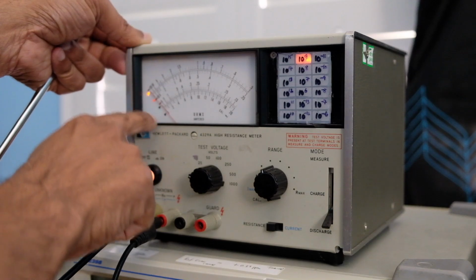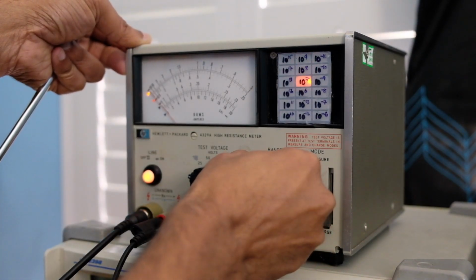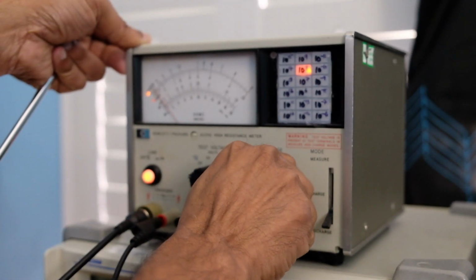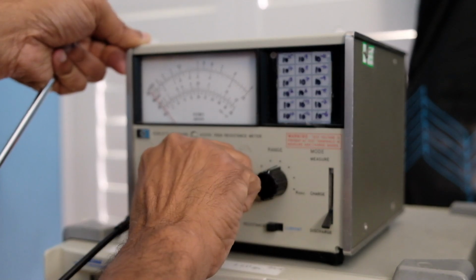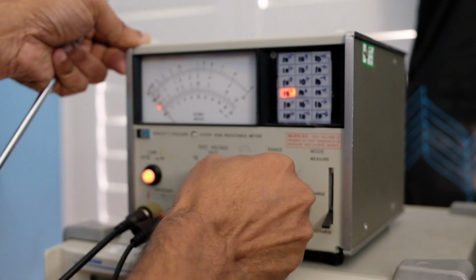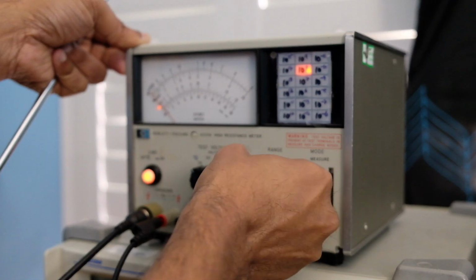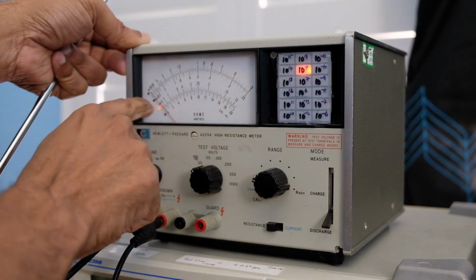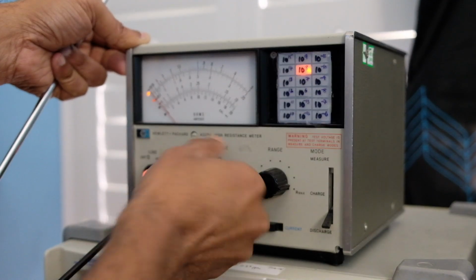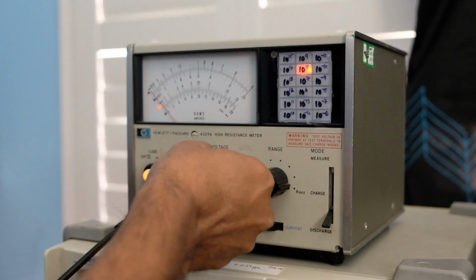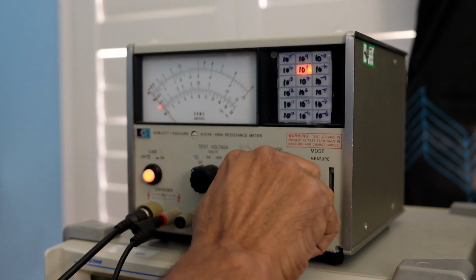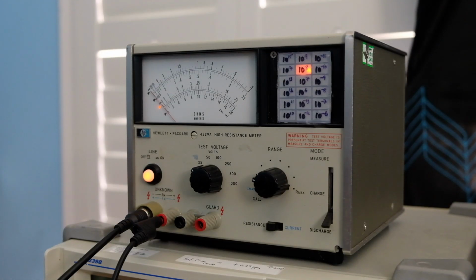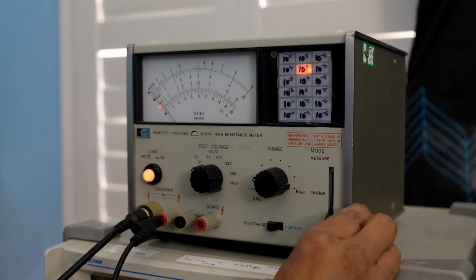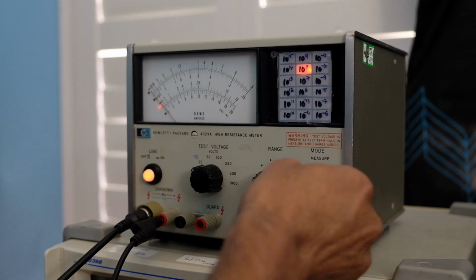So you can see on the left side over here the scales that are being indicated. You can see it switches to different scales depending on the voltage that you set. There are 3 or 4 scales over here. So I'm going to just measure it at 25 volts. This is going to be 32 mega ohms, so this is 100 mega ohms full scale. Resistors don't require being charged up, so we can immediately go to measure.